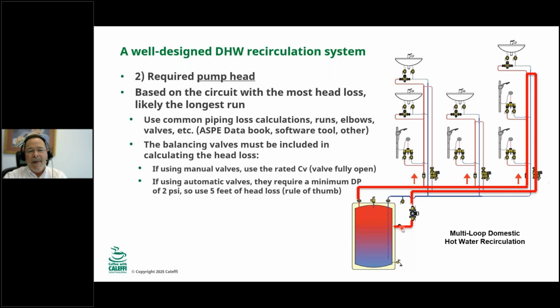If you're using automatic valves or constant GPM valves, some people call those dynamic valves or pressure independent valves, each of those, depending on who makes them, they have a minimum DP requirement. Ours have a minimum DP of 2 PSI. So as a rule of thumb, you can use 5 feet of head loss across an automatic balancing valve like the type that we make. It's a question because they don't really have a CV. These type of pressure independent valves don't have a CV, and we get the question, well, how do I figure out what the head loss is across those? Just use 5 feet of head loss for those.